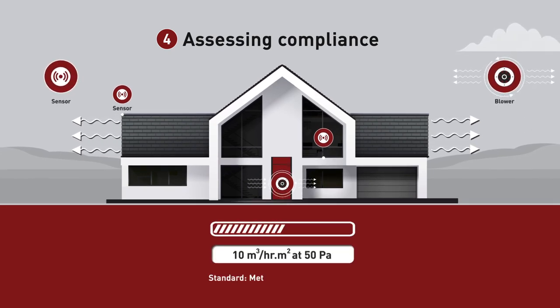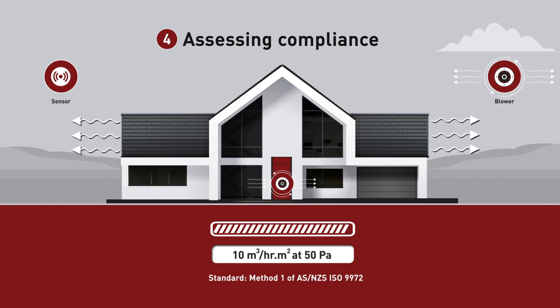Step 4: Assess compliance. Compliance is checked using air permeability at a 50 pascal pressure difference. Air permeability is measured in cubic metres per hour per metre squared. To achieve compliance, the measured air permeability must be no more than 10. When applied to homes, this is broadly equivalent to 10 air changes per hour.